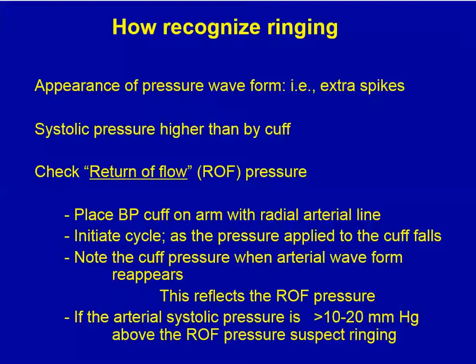Where I left off was about how to recognize ringing. I stated that one method is checking the return of flow pressure, and if the arterial systolic pressure from the arterial line is more than 10 to 20 millimeters above the return of flow pressure, you should suspect ringing.